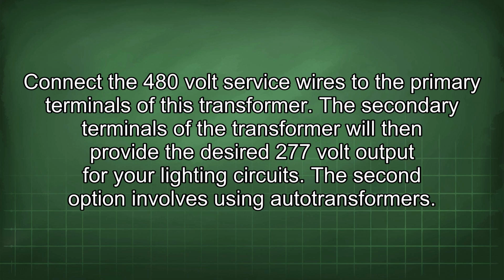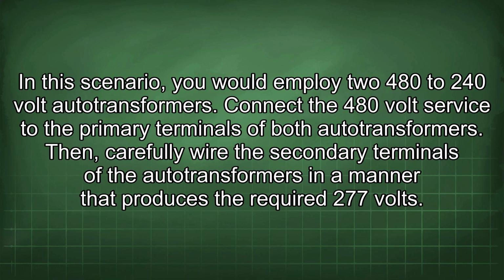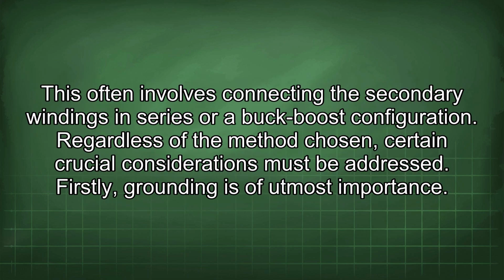The second option involves using autotransformers. In this scenario, you would employ two 480 to 240 volt autotransformers. Connect the 480 volt service to the primary terminals of both autotransformers. Then carefully wire the secondary terminals of the autotransformers in a manner that produces the required 277 volts. This often involves connecting the secondary windings in series or a buck boost configuration.